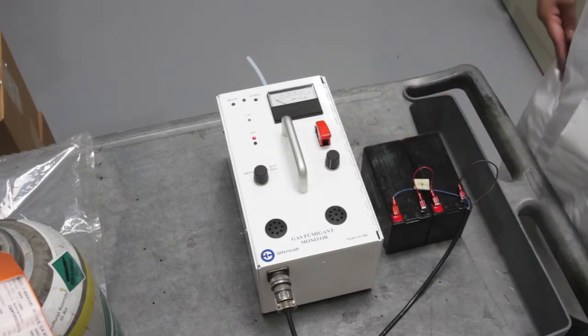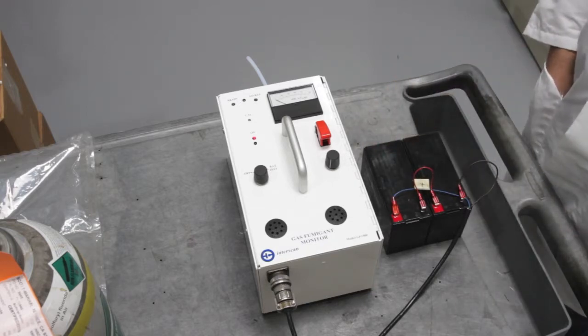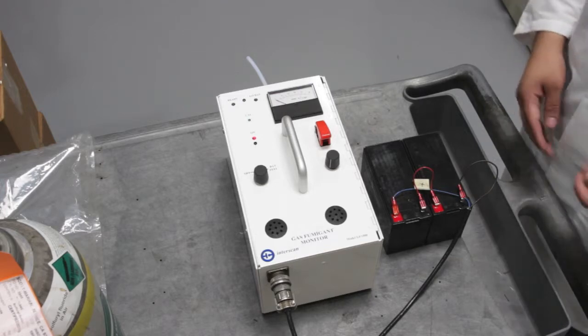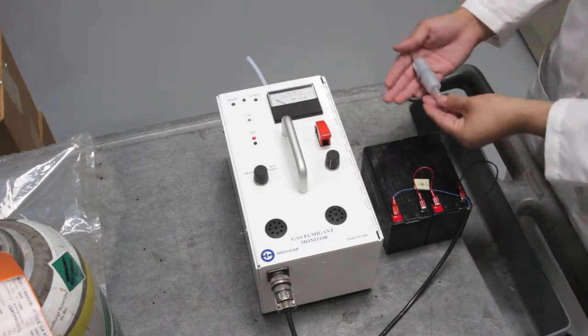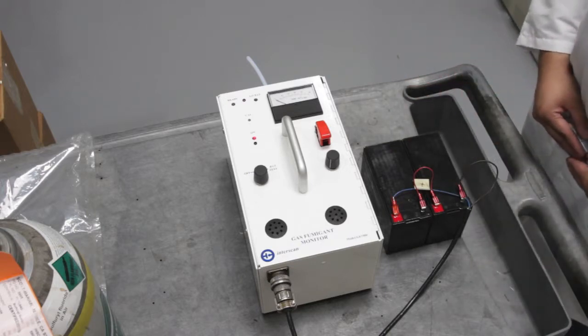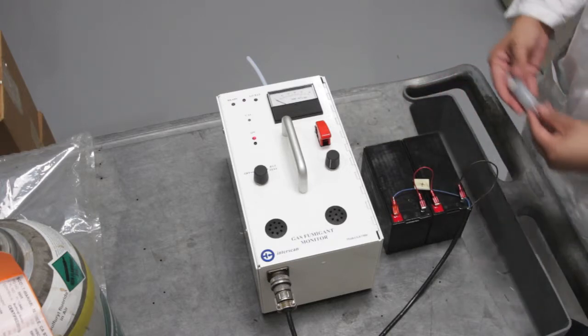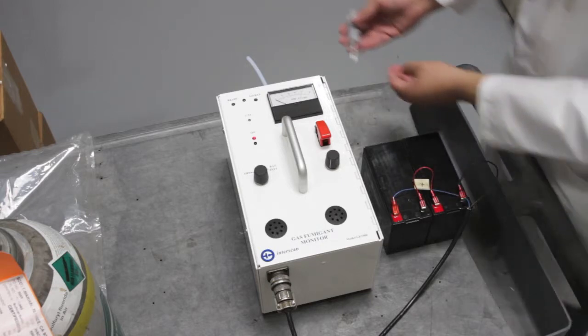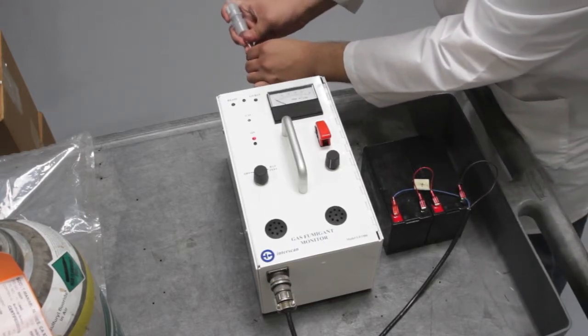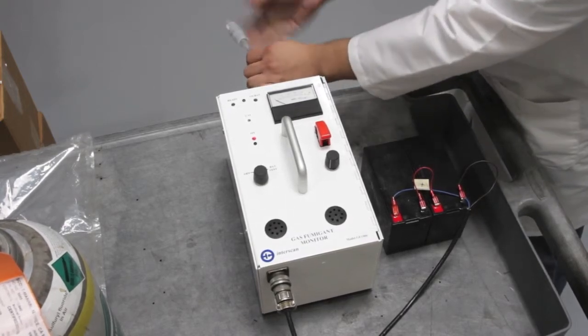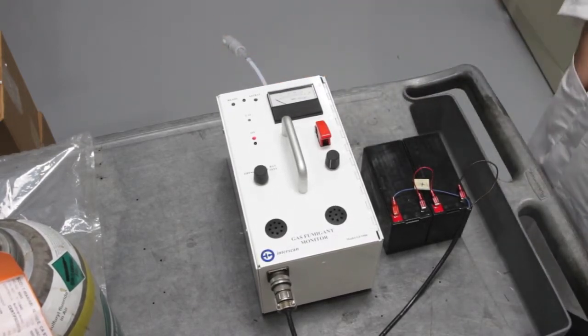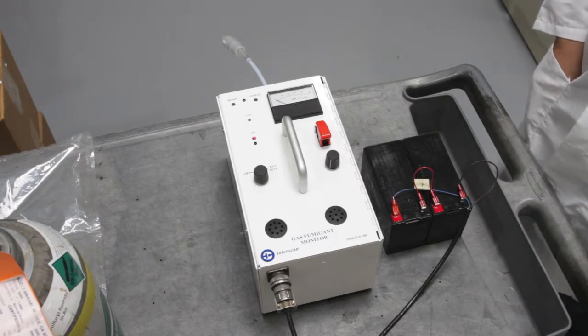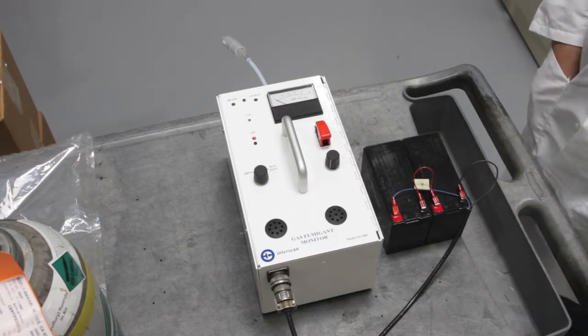If zeroing in an environment which may have other cross interferences, a zero filter should be used. Contact Interscan for additional information. When using the zero filter, connect the zero filter to the inlet of the analyzer. Continued drifting after the ready light comes on will create an erroneous zeroing of the analyzer. Additional runtime may be required if this condition continues. Remember, a true zero cannot be achieved.